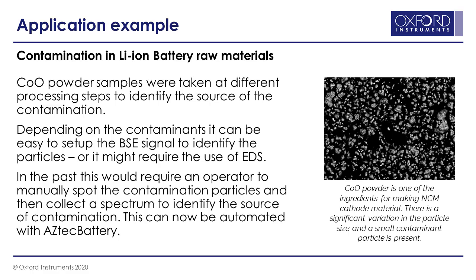We can use backscatter imaging, filtering on size to look at particles above one micron, and then use EDS to determine their chemistry. Before automated solutions such as Aztec Battery, an operator would have to manually find, identify, and collect data from particles. This is now fully automated with Aztec Battery — we set the thresholds and Aztec Battery takes control, collects the chemistry, and classifies the particles.